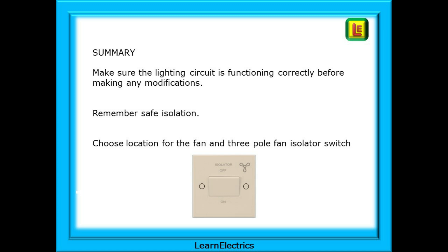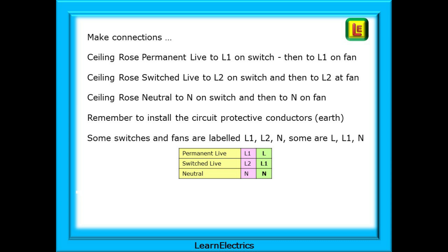That is a brief introduction to bathroom fans. In summary, always make sure that the lighting circuit is functioning correctly before making any modifications, and do remember safe isolation. Then choose a location for the fan and 3-pole fan isolator switch. Now make the connections: ceiling rose permanent live to L1 on the switch, then to L1 on the fan; ceiling rose switched live to L2 on the switch, then to L2 on the fan; ceiling rose neutral to N on the switch (sometimes labelled L3), then to N on the fan. Remember to install the circuit protective conductors — the Earths. Some switches and fans are labelled L1, L2, and N, and some are labelled L, L1, and N depending on the manufacturer, and this little table shows this.